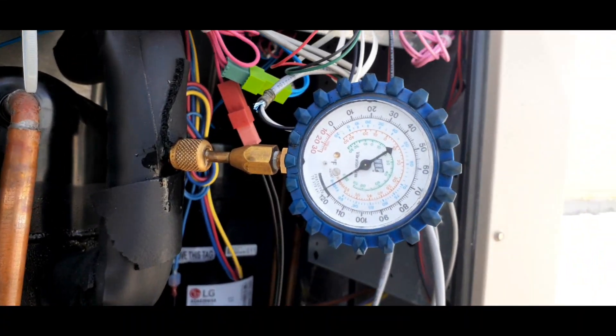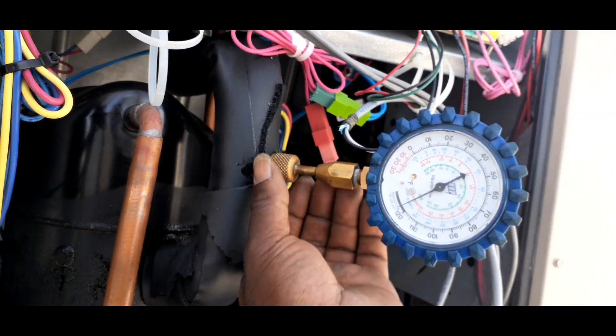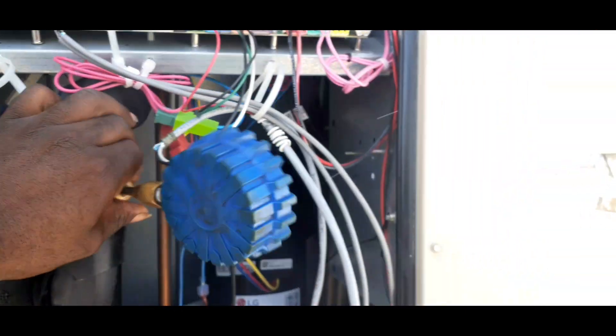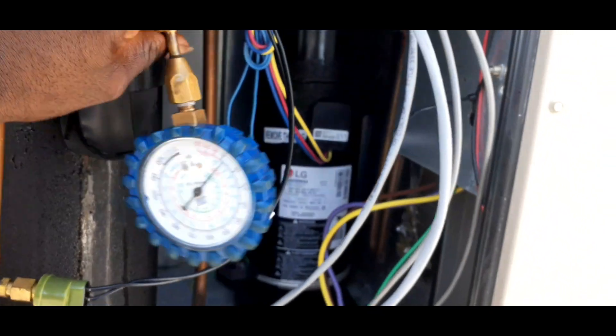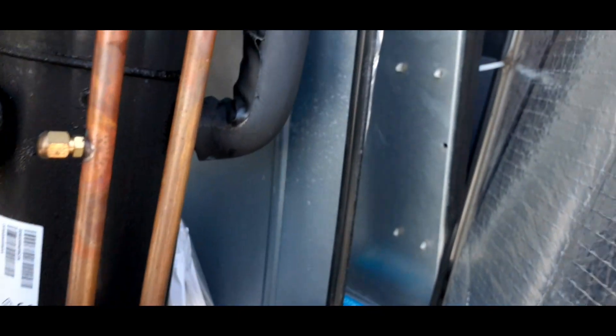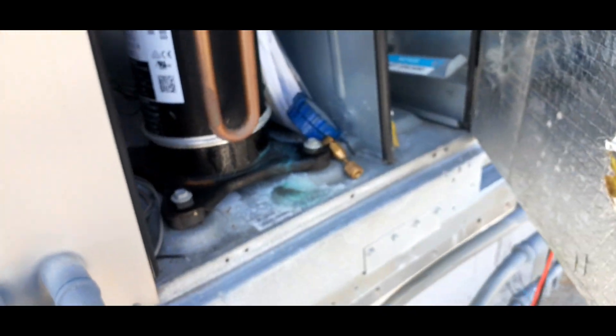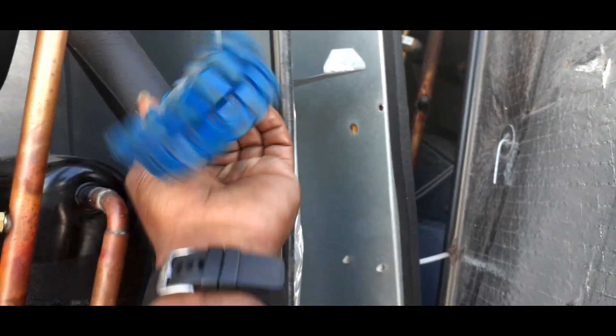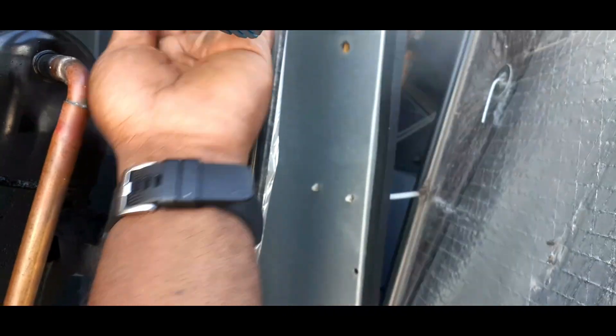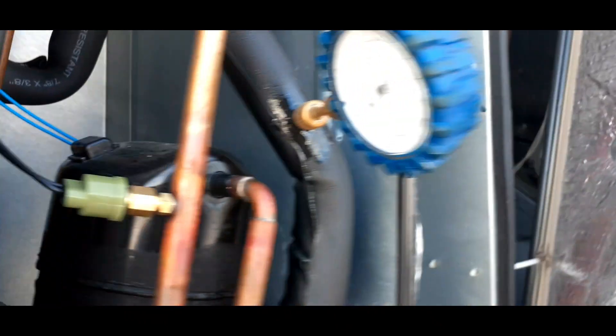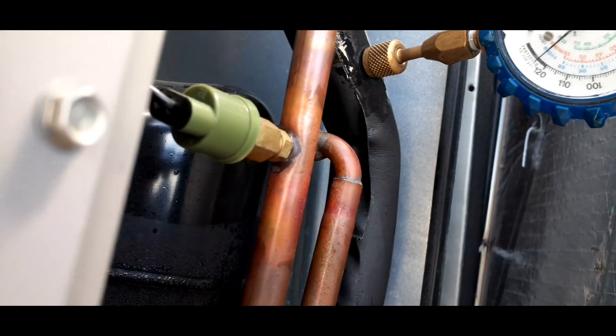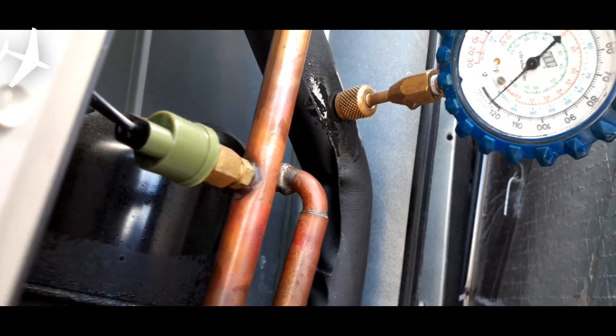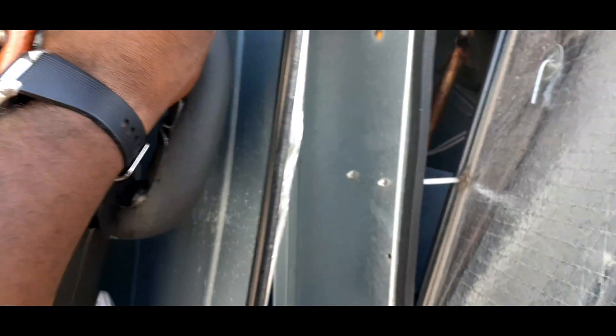All right, so we're at 120 on second stage. This unit does have some refrigerant in it. Not going through checking the superheat, but just want to make sure everything is going to be cooling until we come out. You can also hear that adjustable pulley. I don't know if you can hear it in the background, but I can hear it. I got that on order along with a new motor. And well, we had about 120, 130, so that looks pretty good.